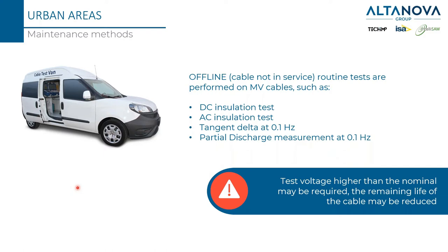Some of these tests are insulation tests applying DC or AC high voltage, or they perform tangent delta or partial discharge measurement at the very low frequency of 0.1 Hz. Whenever we apply high voltage — meaning around the nominal voltage of the cable — we are stressing the cable. Sometimes we also have to apply a voltage higher than nominal in order to amplify the signals we are looking for, and this can sometimes reduce the remaining life of the cable.